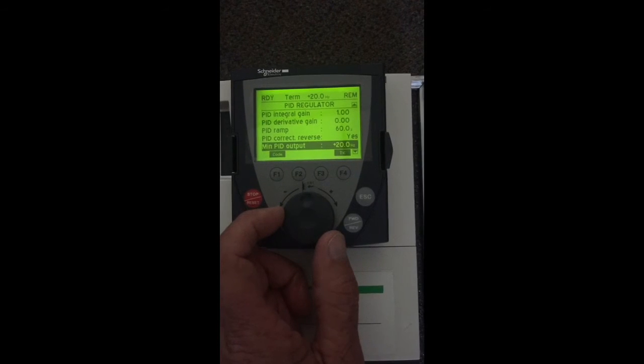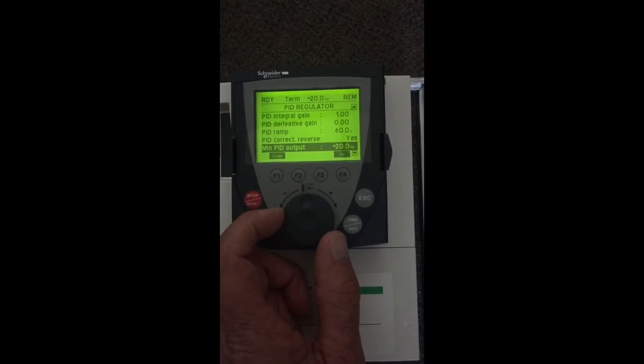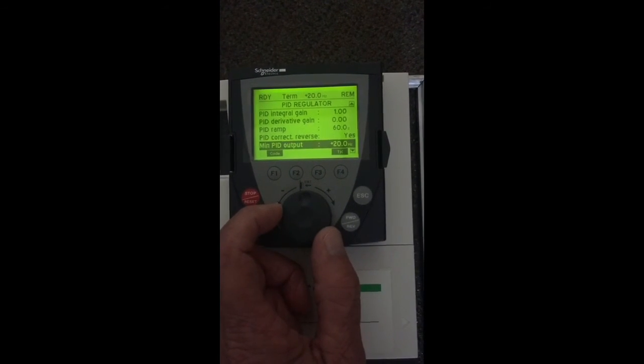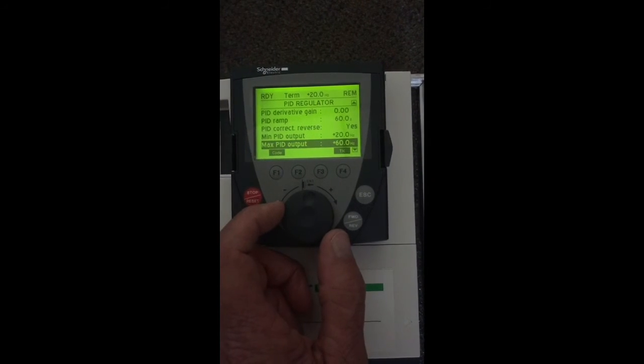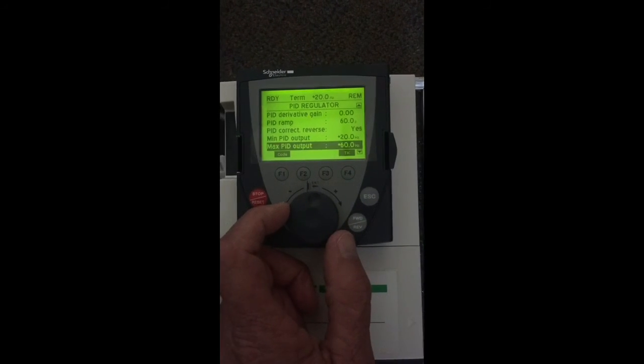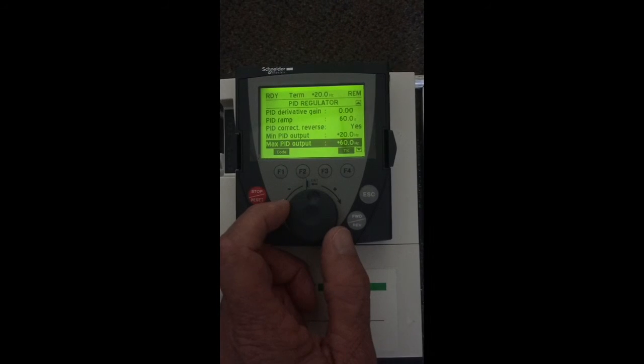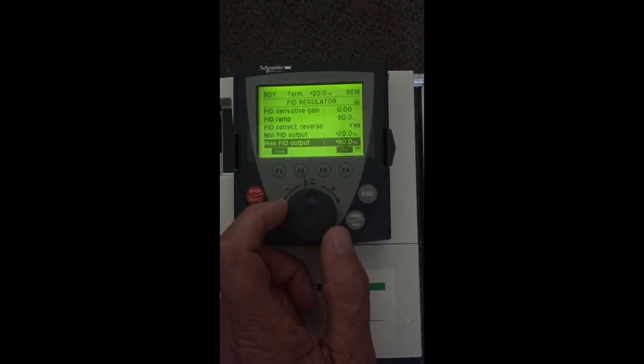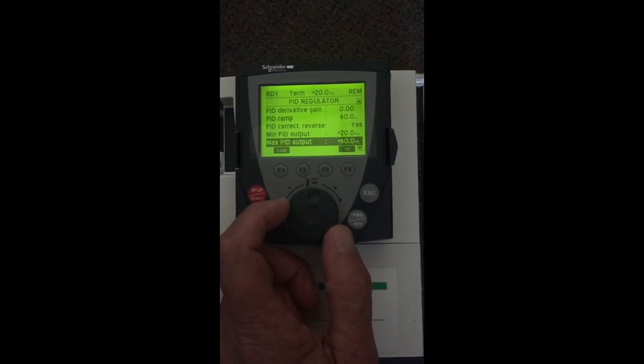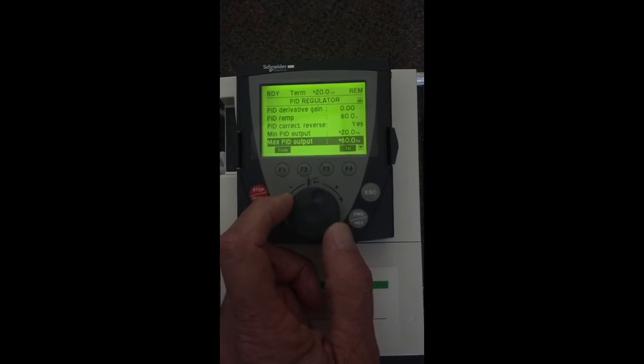Minimum PID output, when it's at its low end, it will fall off to 20 Hertz. When it's at its upper end, it will be at 60 Hertz. So this is your basic speed control in between 20 and 60 Hertz for the temperature transmitter range.